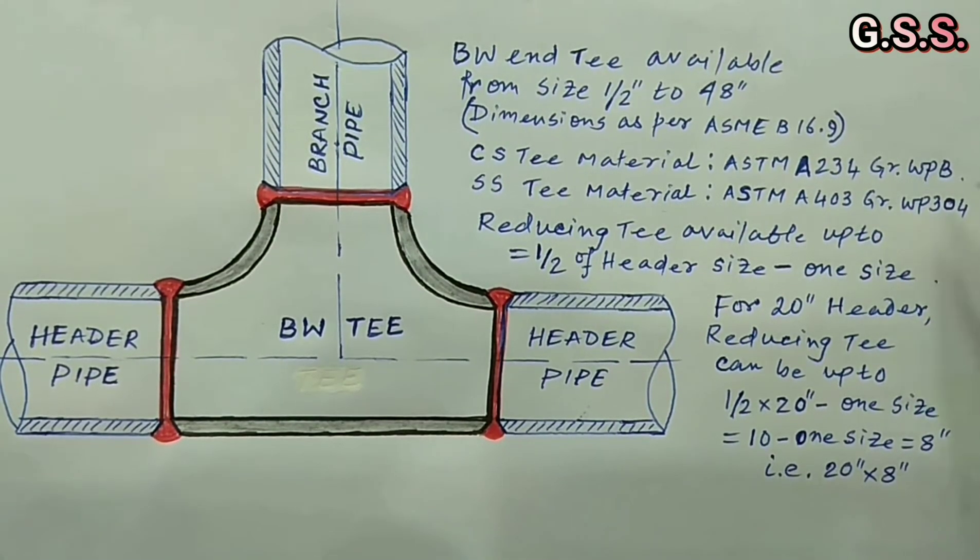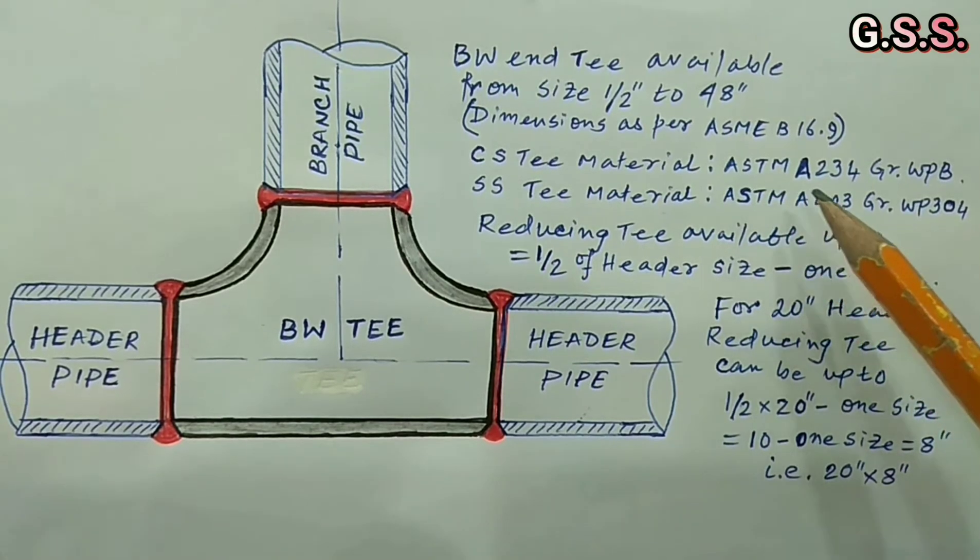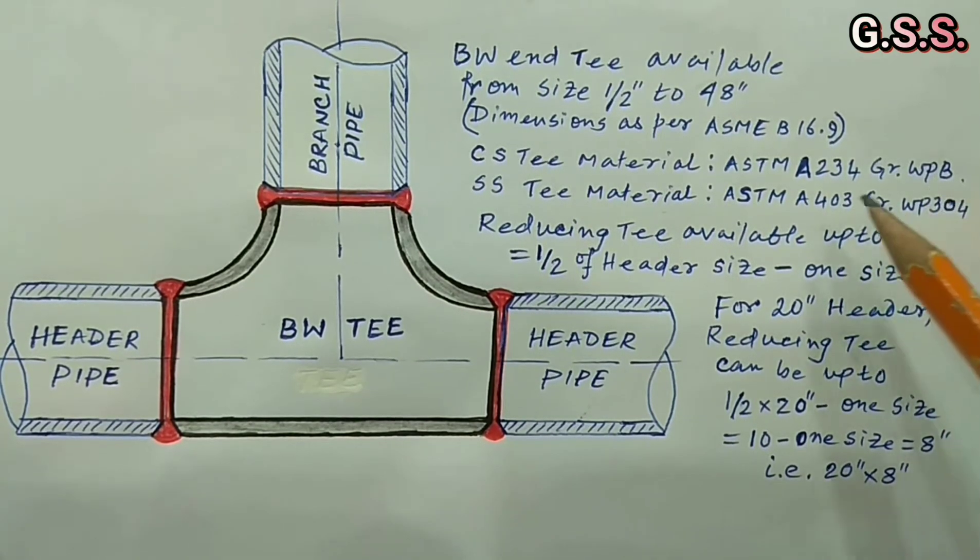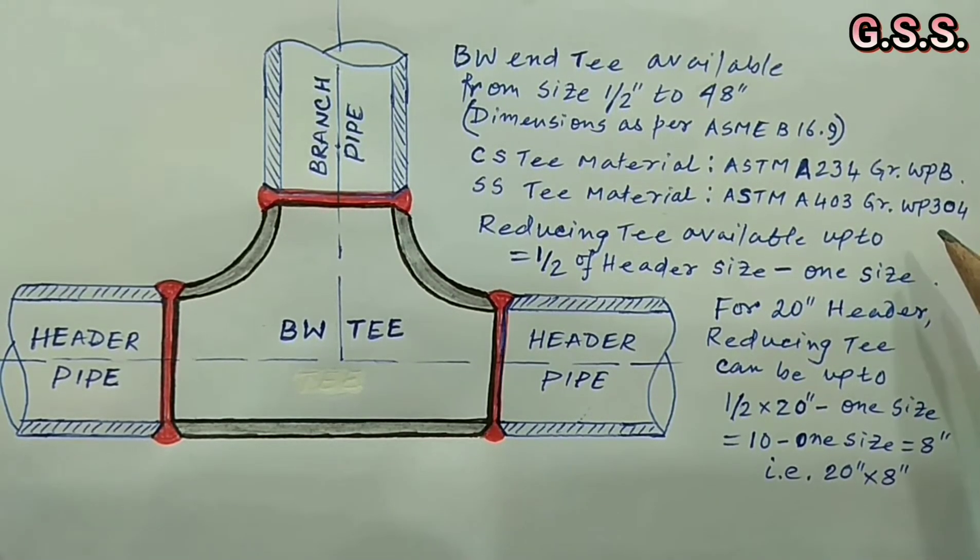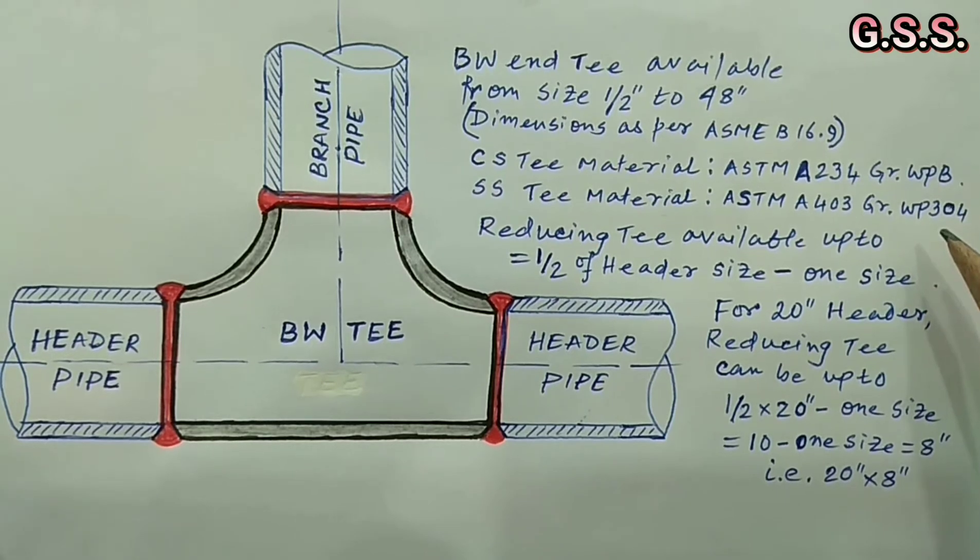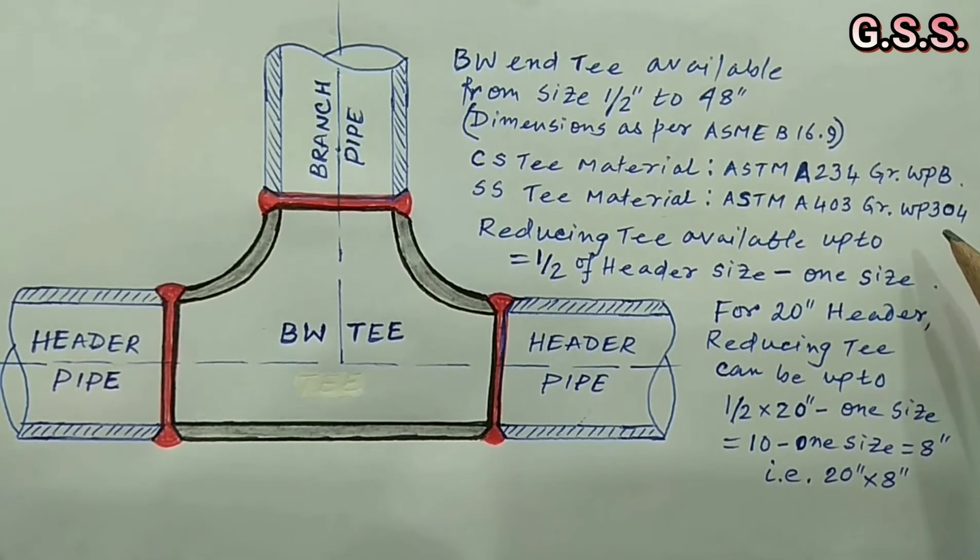Commonly used T material is as per ASTM A234 grade WPB for carbon steel T and ASTM A403 grade WP304 or WP304L or WP316 for stainless steel T.